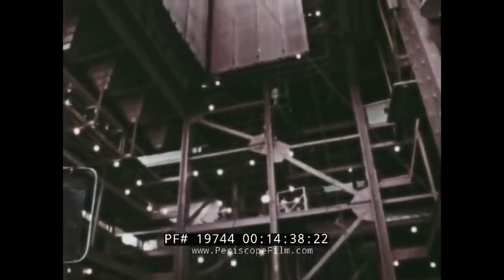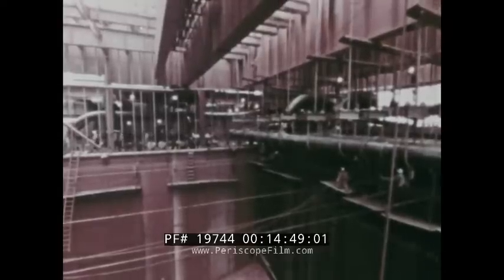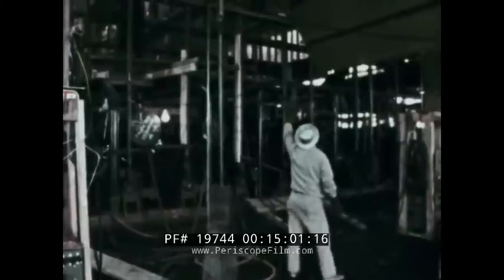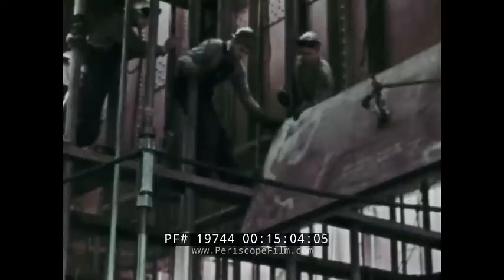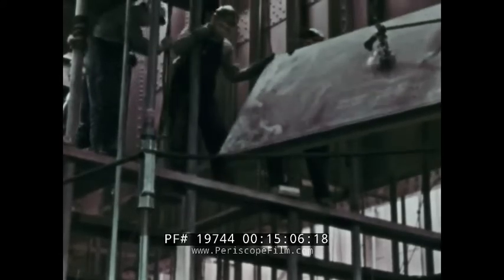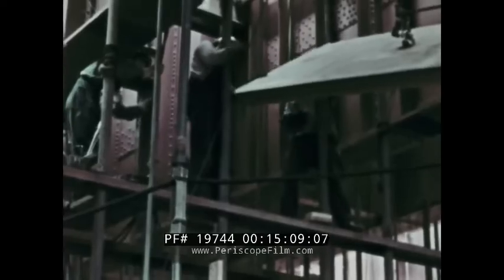Paradise boilers were the largest in the world at the time they were installed. Structurally, the continuous tubing which encloses each of the furnaces is a huge box 163 feet high, 63 feet long, and 32 feet wide. Each boiler produces 4,900,000 pounds of steam per hour, consumes 300 tons of coal an hour, and operates at a pressure of 2,400 pounds per square inch. Its design is the once-through single reheat type.